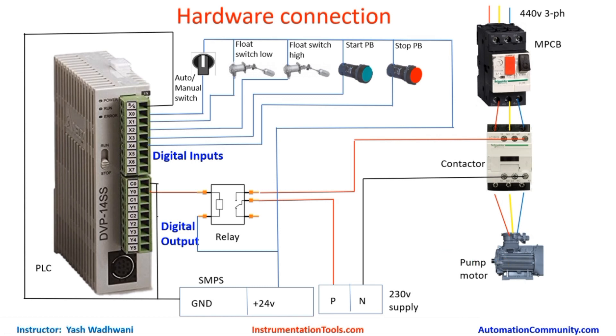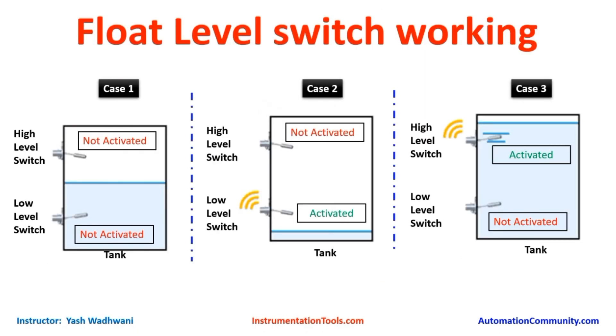Before moving ahead, we need to understand the working of the float switch. In normal condition, when the water is at a normal level — above the low level and below the high level — as we consume water, the level will reduce. When the water level becomes lower than the float switch level, the switch will be activated and give a signal to the PLC, which will then start the pump.